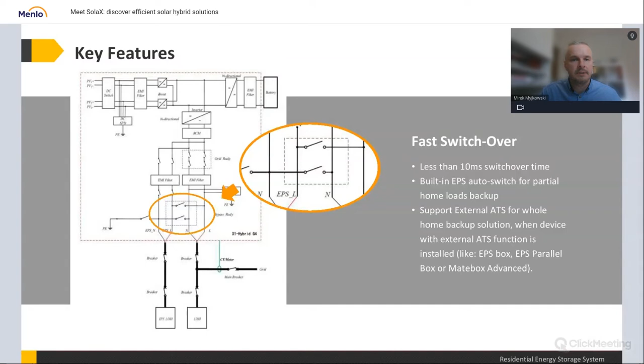But of course it has a limitation of a little bit over 30 amps per phase maximum. So if the flow from the grid to those EPS loads, those critical loads, in normal operation can be bigger than this, then sorry, we have to go for an external switch, and that's it. Generally, counting, it is double the output power of the inverter, or not more than 20K. That is the limit for those ports in the EPS switch that's built inside. If you need to use the external ATS, then you have to look around for the EPS box, EPS parallel box, and matebox advanced, as I said before.